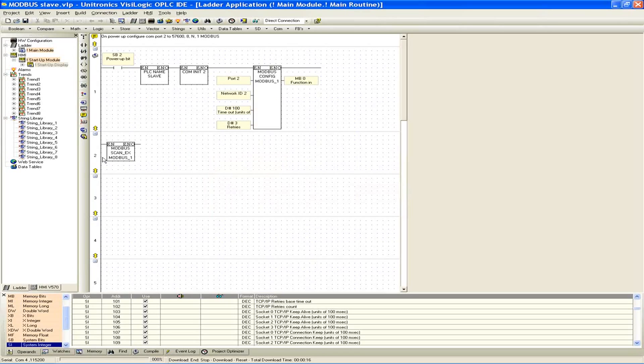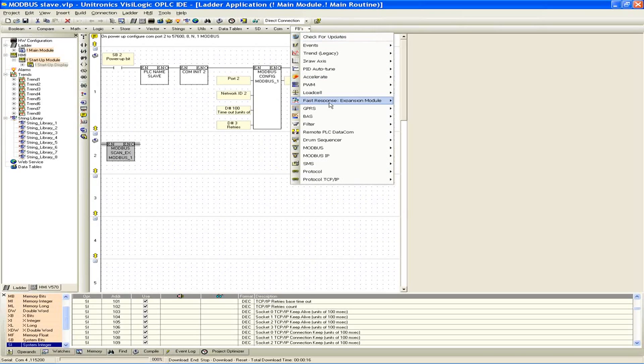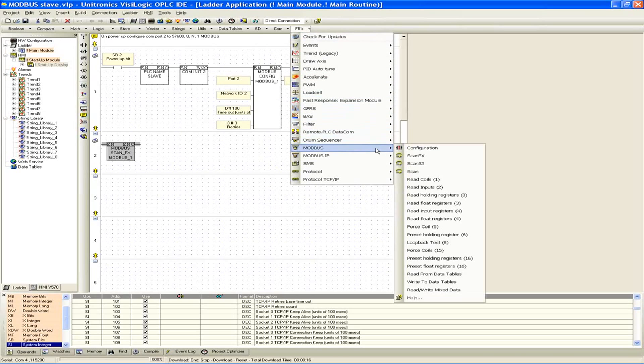So the main thing to make the slave program work and make it tick as a slave, what you want to have is the Modbus scan EX block. So this block, you'll see there's nothing to define in it. If I click it, nothing opens up. You just have to make sure you have this placed down against the rail, and it's going to constantly be scanning and constantly be looking for commands that are being issued from the master device, and it's going to be allowing the master to access its registers by having this scan block. And the scan block is found under function blocks, Modbus, and then scan EX is the one that we're using.